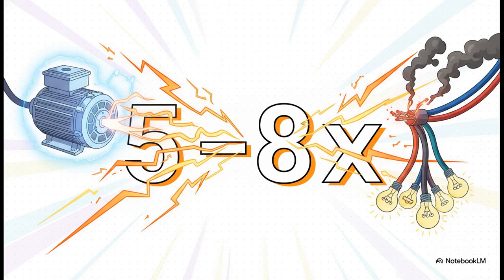When an induction motor starts up, it suddenly pulls an enormous surge of current, anywhere from 5 to 8 times its normal full load current. That's a massive spike. Because of this, the system's voltage takes a sudden nosedive, causing lights everywhere to dim. And worse, this massive current can actually cause cables to overheat, and, in extreme cases, even catch fire. Not exactly what you want happening on your watch, right?